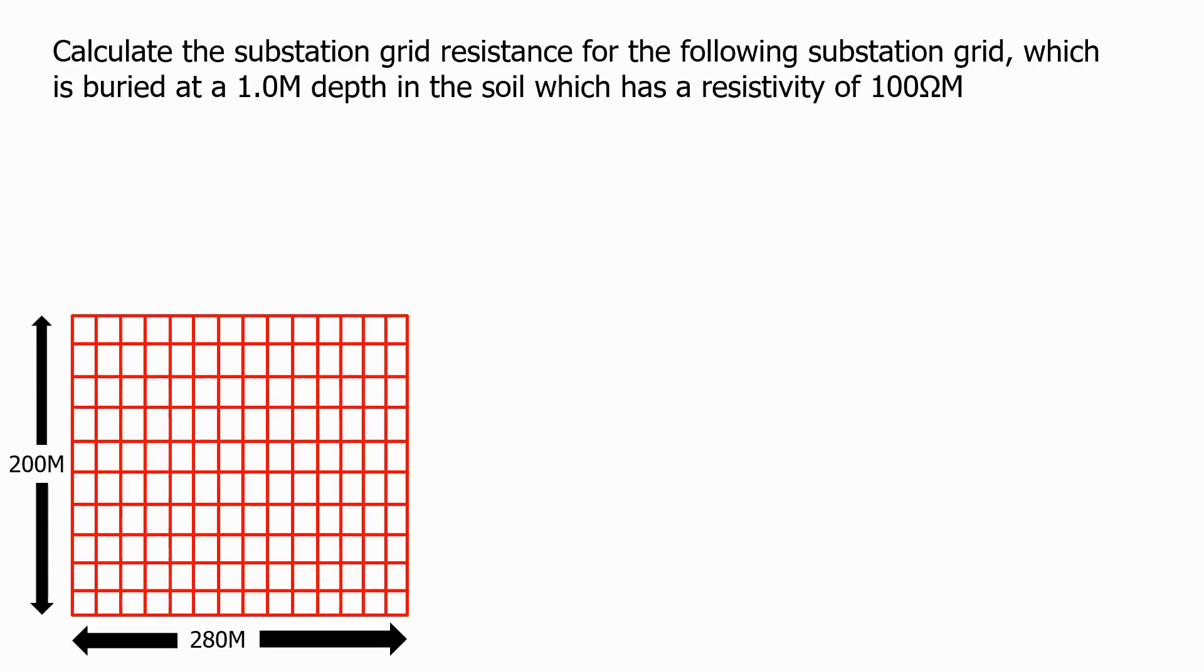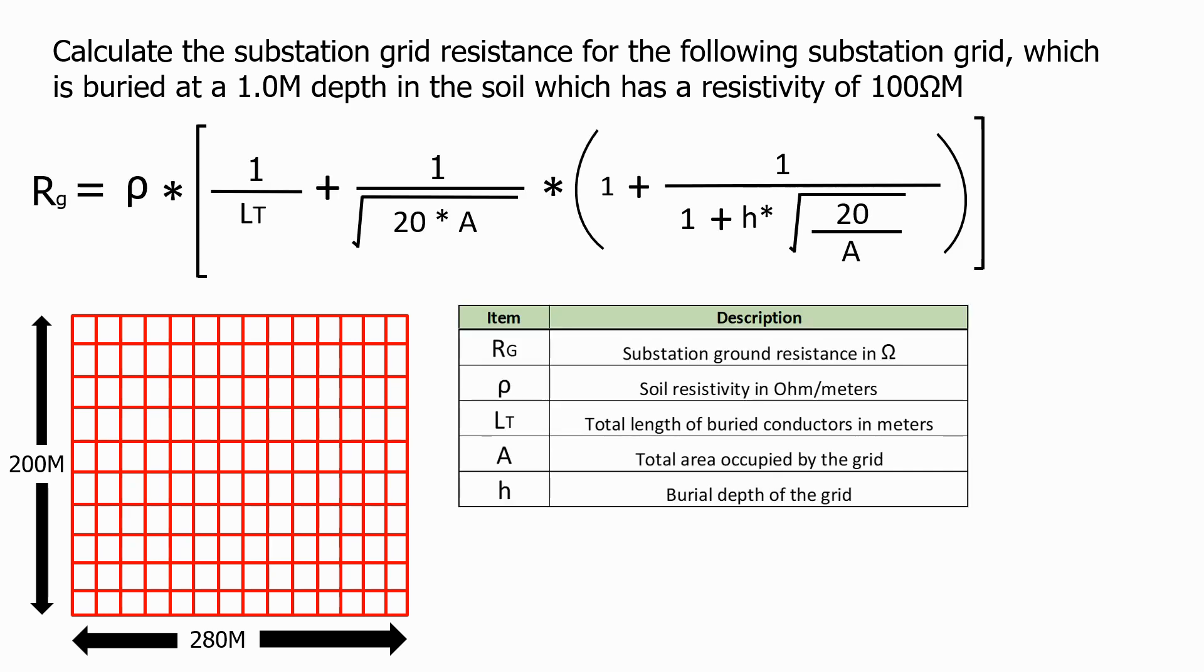Let's do a worked example. Calculate the substation grid resistance for the following substation grid, which is buried at a 1.0 metre depth in the soil which has a resistivity of 100 ohm metres. Here's our standard formula for the grid resistance.